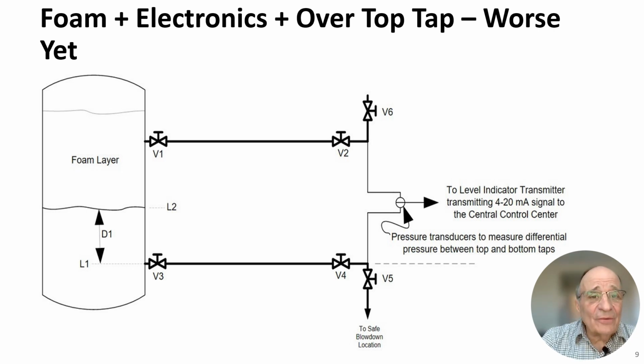Again, I'm showing you now a foam layer that is even higher, yet it's above this second tap. So now we have a double problem related to foam. The foam is impacting this pressure as well as this pressure, complicated by the fact that the instrument person has to calibrate this correctly, and now the operator is dealing with an even more complex set of phenomena that may be giving a false reading.